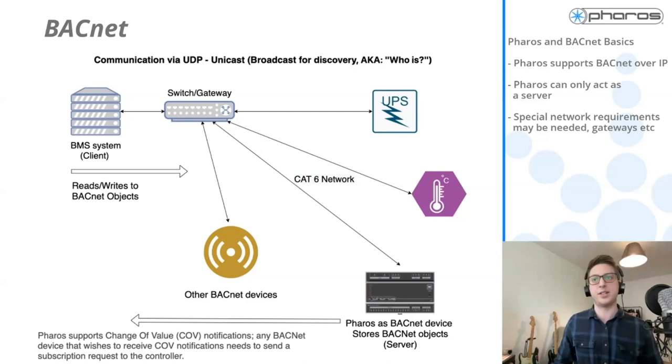However, in this scenario, using the Bacnet IO module, we only support Bacnet acting as a server. It can't act as a client like it does in Modbus. It's only going to be a server device. And we only support Bacnet over UDP, so over a computer network. We don't support any other protocols.